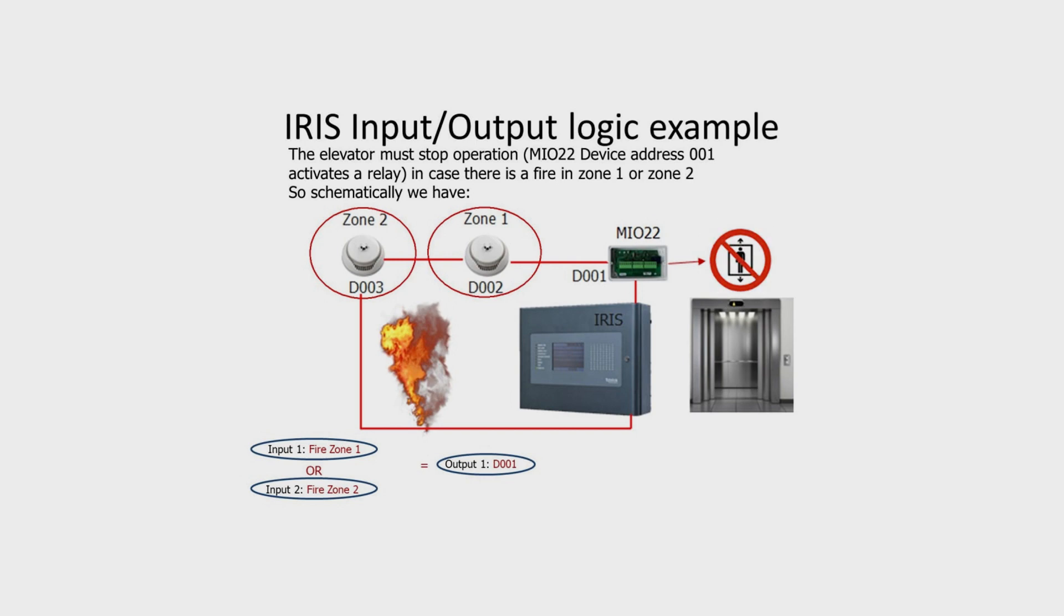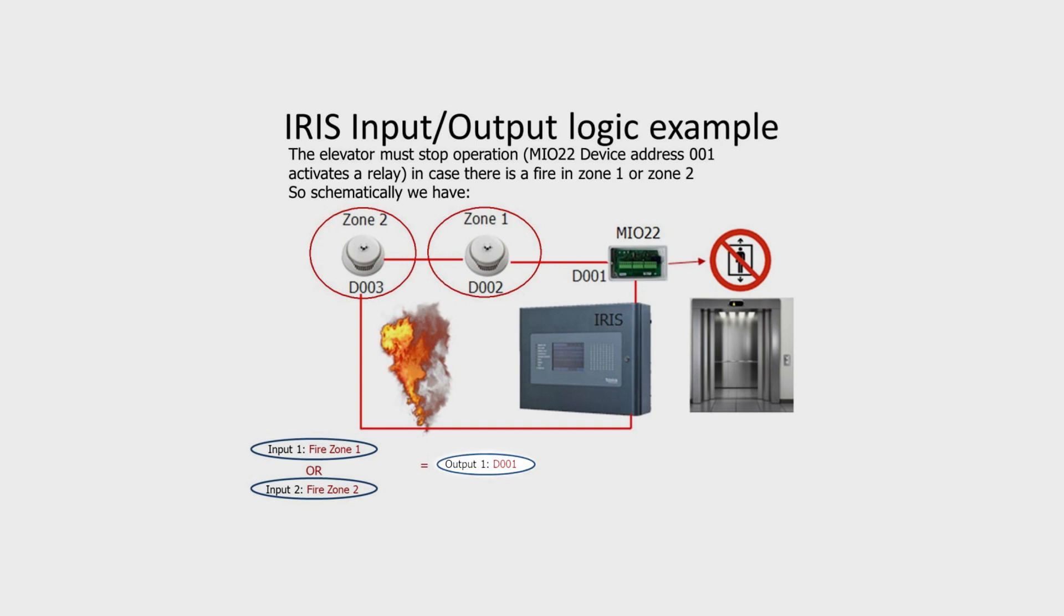What we need to do is create input 1 for fire in zone 1 and input 2 for fire in zone 2. They are going to be in OR logic in relation to the output action which is going to control the relay output of the Mio 22.